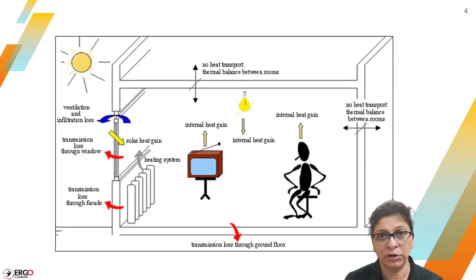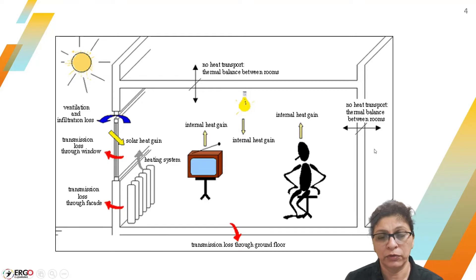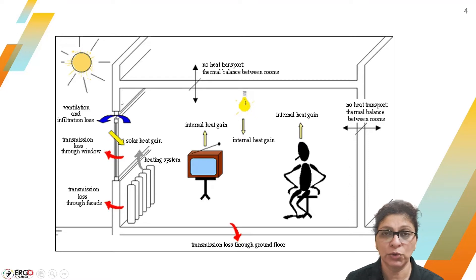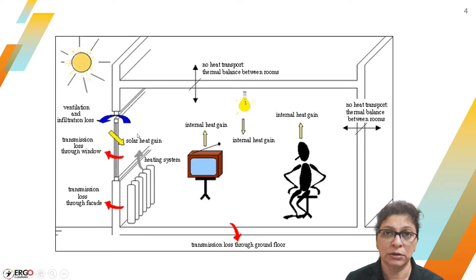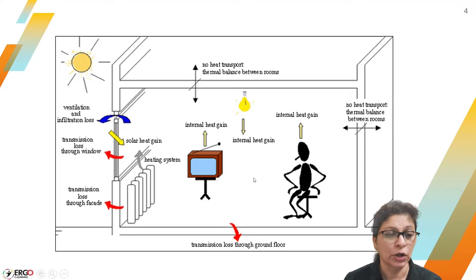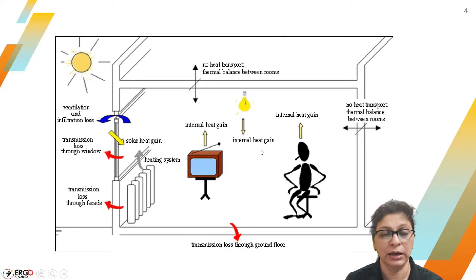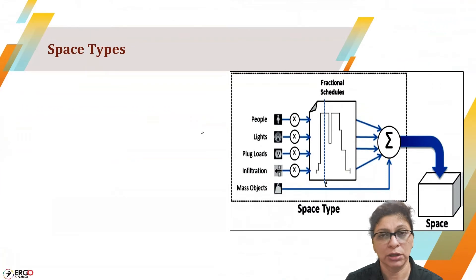There is a diagram showing how different types of loads act on the building. The building is thermally connected with the upper floor as well as with the side walls, so there are no heat loads across those two boundaries. It is connected to the atmosphere through one face, and on this face there exists one window, so there will be solar heat gain or heat loss based on the weather and location. Equipment loading such as heating equipment will add load to the room, all other electric gadgets will add sensible heat load, and human occupancy will add sensible and latent heat load.